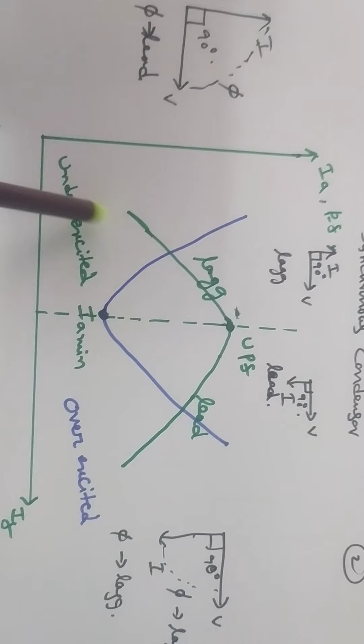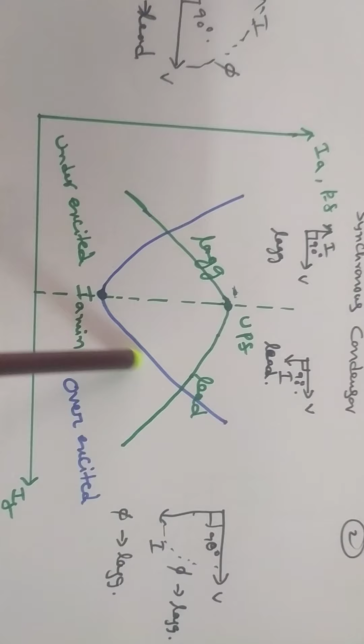When you come to the V and inverted V curves of the synchronous condenser, the x-axis is field current, the y-axis is armature current as well as power factor. So this is the IF versus IA at a particular point. The power factor of the machine is unity power factor corresponding to nominal excitation. The current is minimum, IA minimum. It draws minimum current at unity power factor.